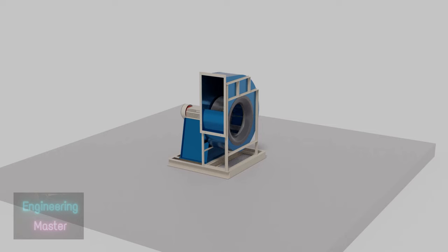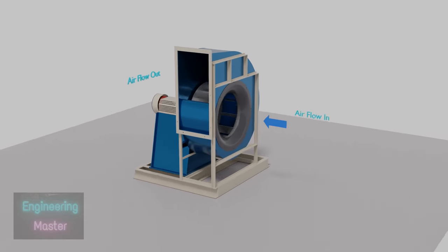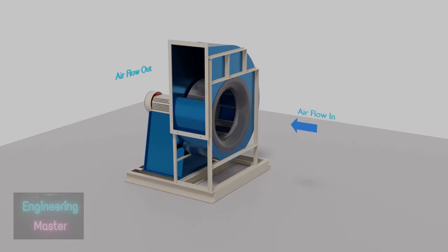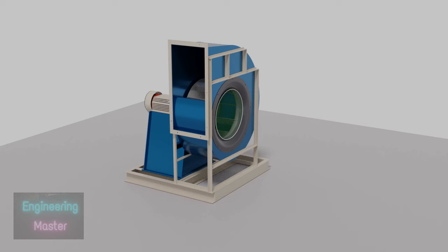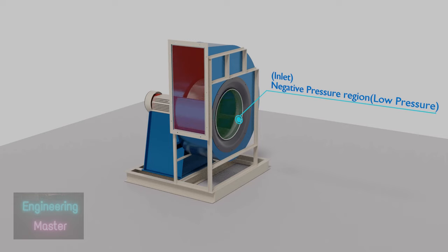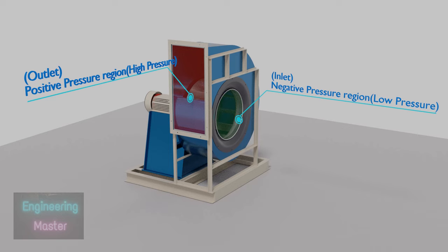As the impeller starts rotating, air enters the fan axially and it will be displaced radially. Impeller will displace the air at the inlet and making a negative pressure region at inlet. Kinetic and pressure energy is imparted to air, which in turns makes the outlet region a positive pressure region. So air will be moved from high pressure region to low pressure region. Inlet is low pressure region, so air enters through inlet. As the outlet is a positive pressure region, the air will be displaced through the outlet.